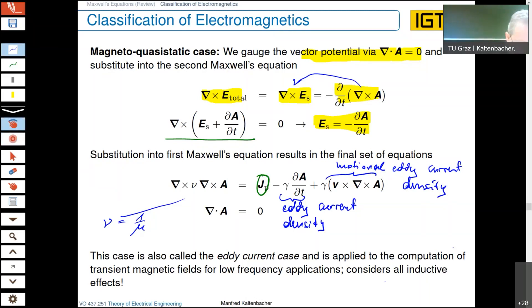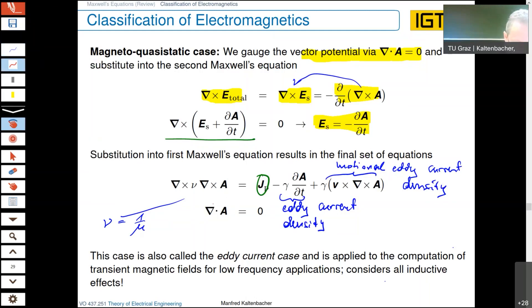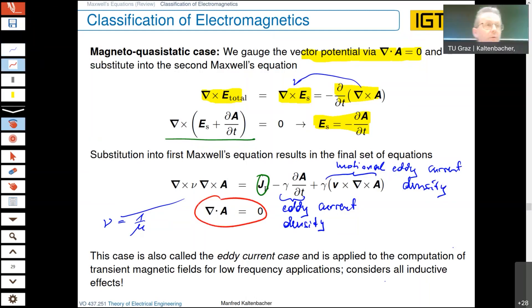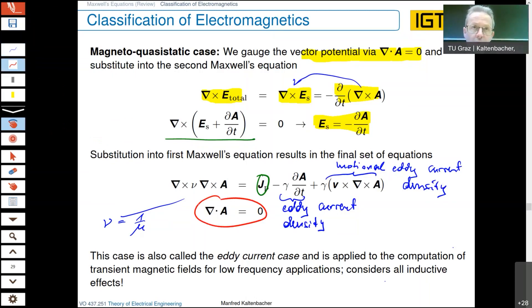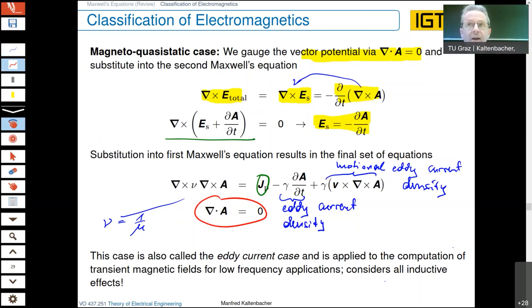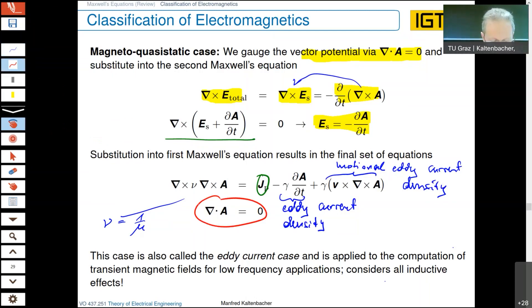That is why, for example, you do not use a massive iron core but instead a laminated iron core — a typical example being the transformer, where the core is made of many thin electrical steel sheets, about 0.3 millimeters thick, with high permeability, in order to keep the conductivity low.